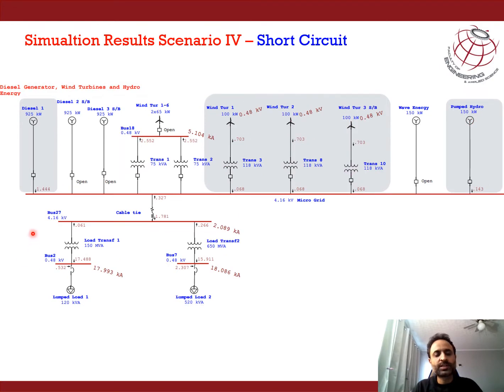For the short circuit levels in this case, scenario 4, the fault addition to the bus by the pump hydro is 0.143 kiloamps, in addition to the wind turbines and the diesel generator. The total fault at the load bus is within the limits, at 18 kiloampere or 18,086 amperes.